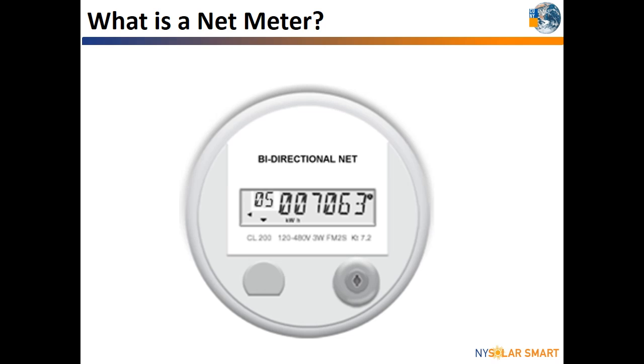It's a digital electric meter that is programmed to calculate the sum or net of energy delivered to your building. You won't actually see a dial on the meter spinning forwards and backwards because it's all digital. However, you will see an arrow pointing left or right to indicate if electricity is being sent to the grid or from it. When the arrow is moving left, excess solar electricity is being exported to the grid. When the arrow is to the right, the utility is sending you electricity.